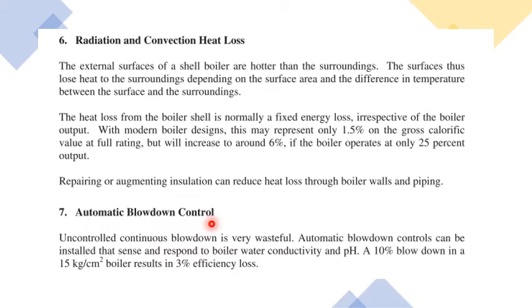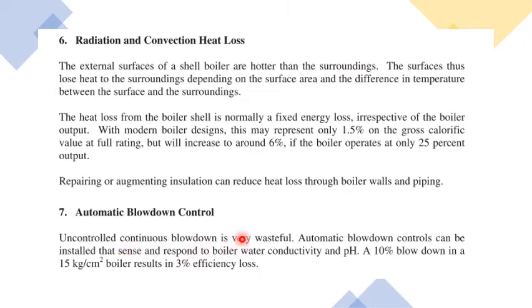The seventh point is automatic blowdown control. There are two types of blowdown — intermittent and continuous. Uncontrolled continuous blowdown is very wasteful. Automatic blowdown controls can be installed that sense and respond to boiler water conductivity and pH. As a reference, a 10% blowdown in a 15 kg/cm² boiler results in a 3% efficiency loss, so controlling blowdown is essential.